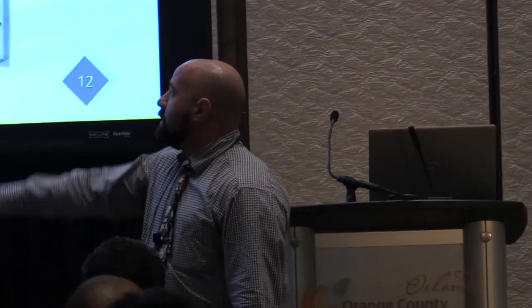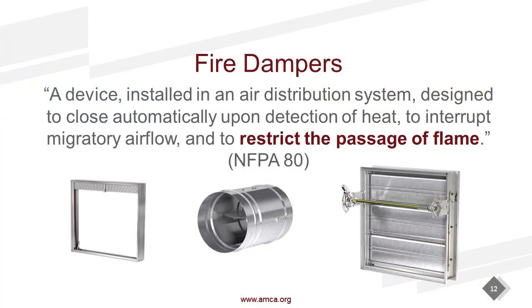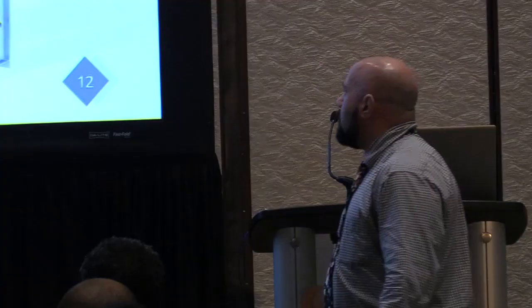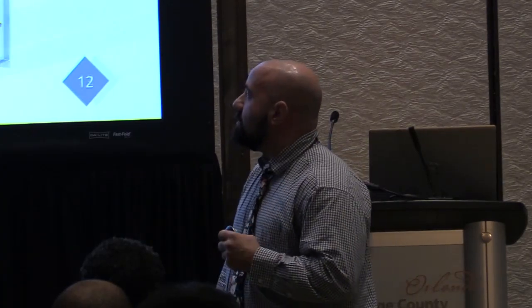That barrier is no longer continuous. That damper makes up the hole in the event of a fire. Some common pictures of dampers. Your extreme left, that's what we call a curtain fire damper, most commonly used and specified. The center is a true round for your round duct penetration, spiral duct, things of that nature. And then we have a multi-blade fire damper. It looks very much like a control damper. It's built very similarly, but it does feature a fusible link and a spring and is a UL rated product.